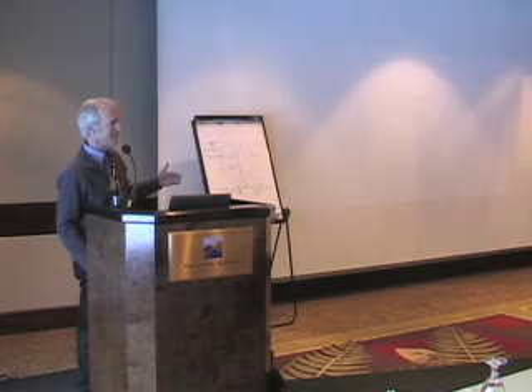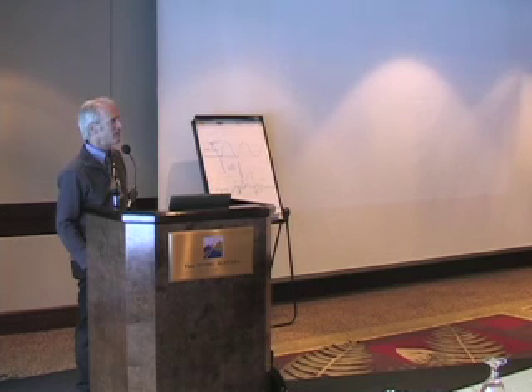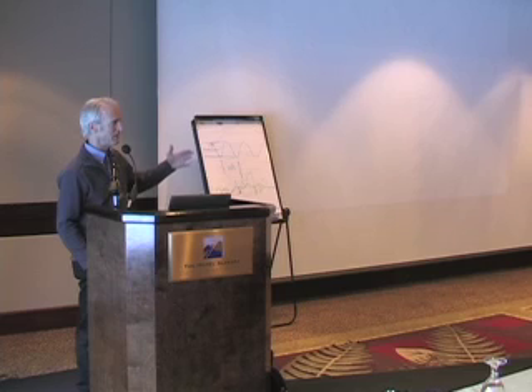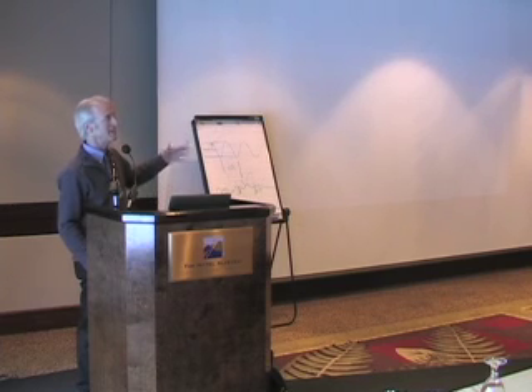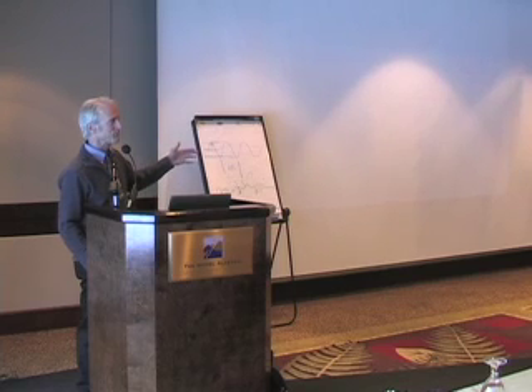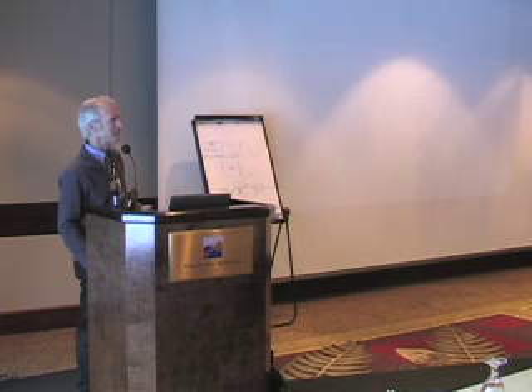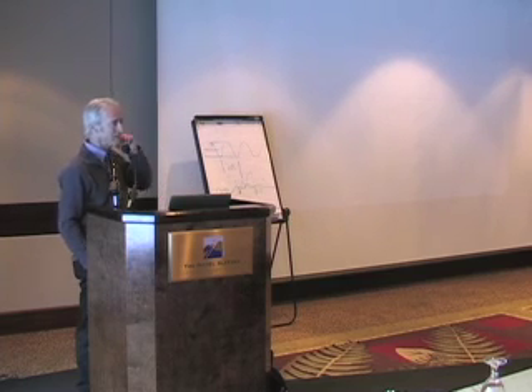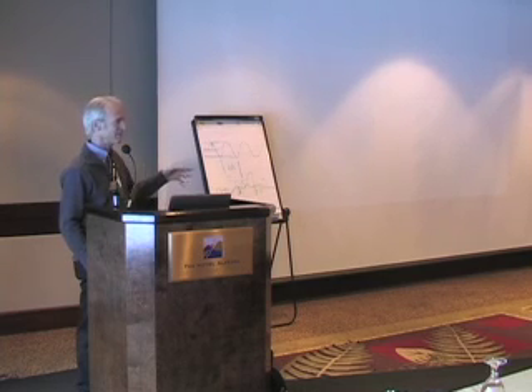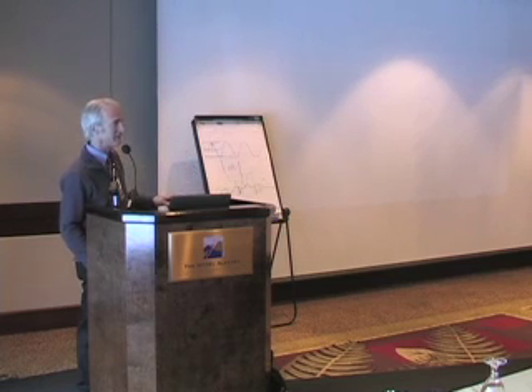Yes, round-trip energy efficiency. Peter may have additional data on that, but I know he deals a lot with energy storage numbers. But in something like a solar PV application, maybe where a battery is going through deep discharge cycles, like a remote cabin that's operating a solar system, you might get the battery fully charged during the day and kind of on float charge, where there's current trickling in, and then discharge it 60 or 80% overnight. If you measure the energy efficiency of that storage, it's going to be much less, because both at the top of the range and the bottom of the range, you lose a lot of energy just in the electrochemical processes in the battery that not too many people understand.